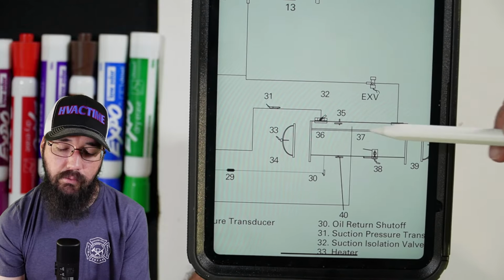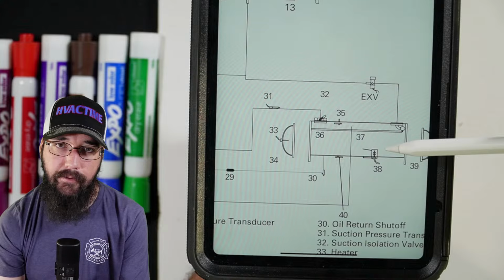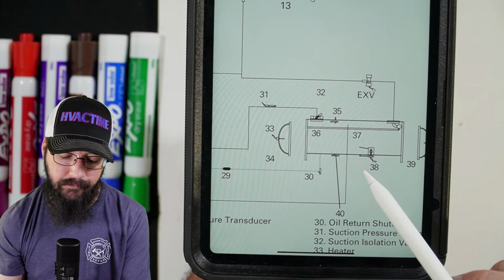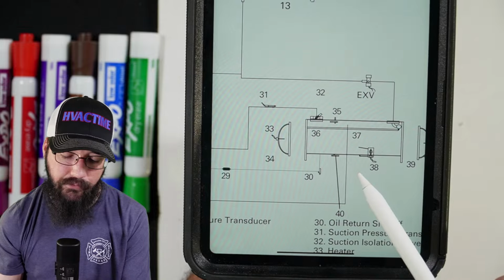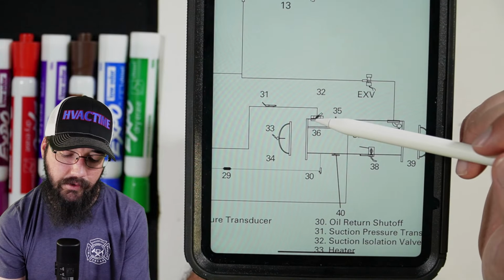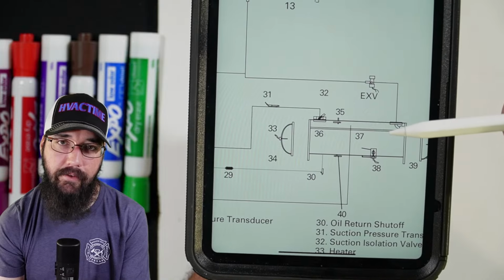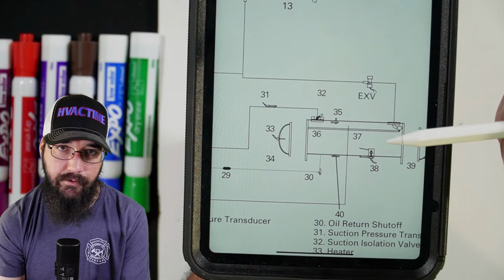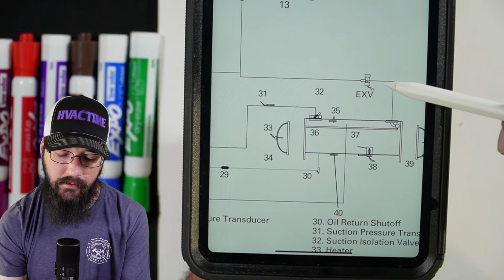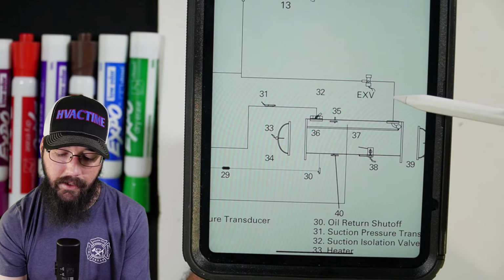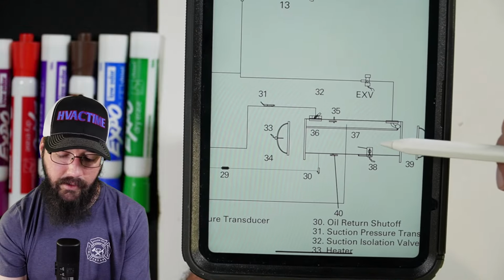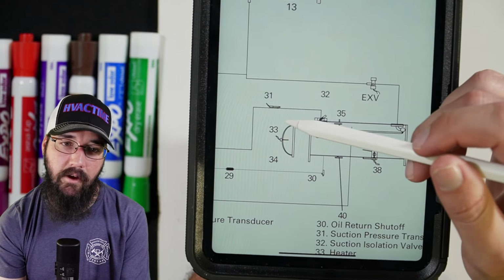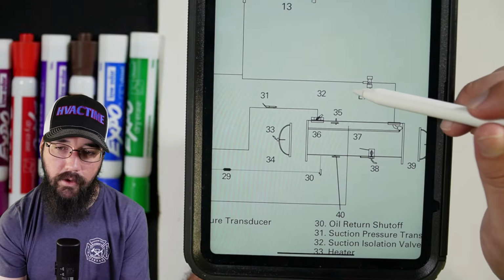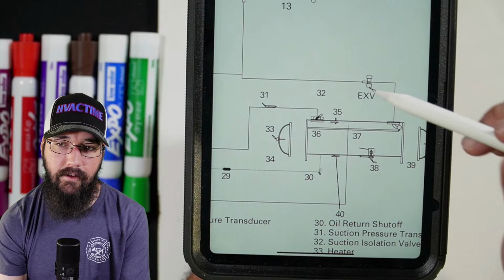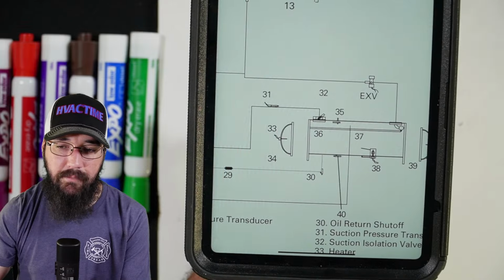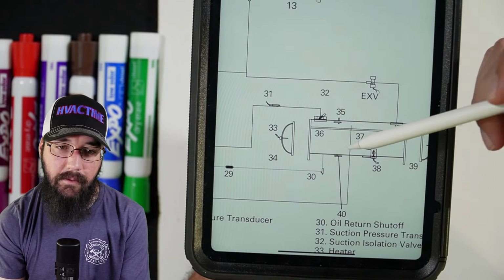This allows refrigerant, as it boils off, to come out into our suction line as a vapor. What doesn't come with that vapor typically, because we're feeding high pressure liquid, a low pressure liquid-vapor mixture, into the evaporator, is the oil. We're just getting vapor coming off of here, and what gets left behind is the little bit of oil that is in here. It stays. So the little bit of oil ends up staying here.